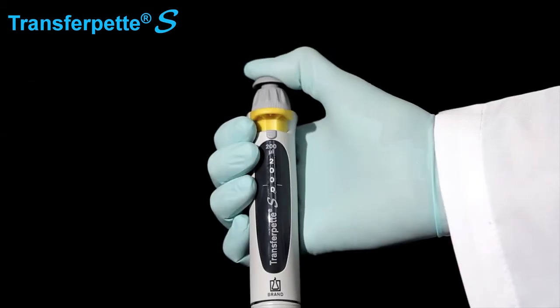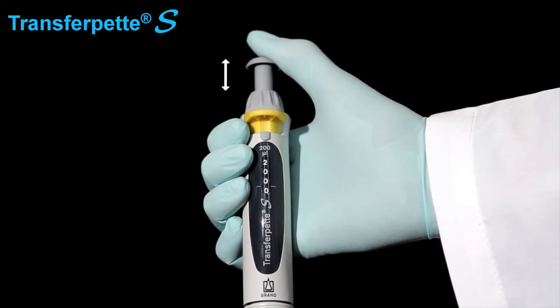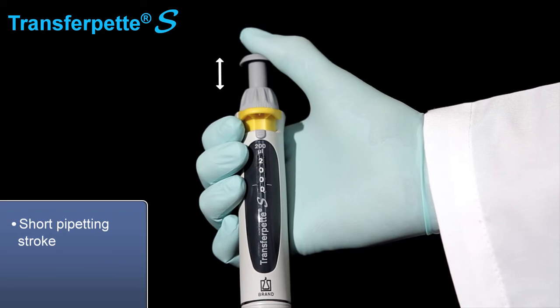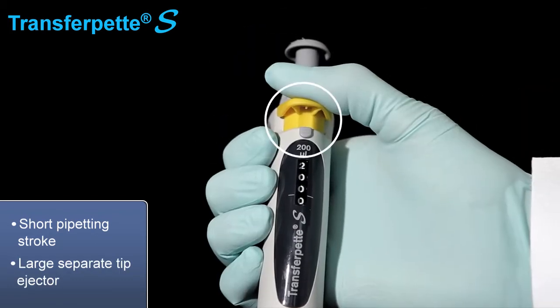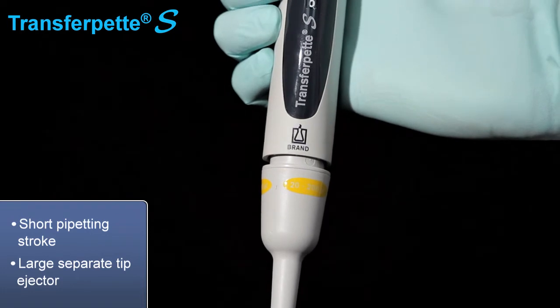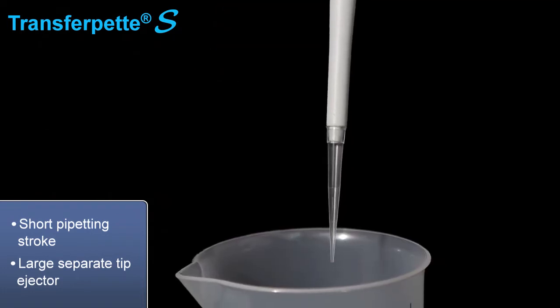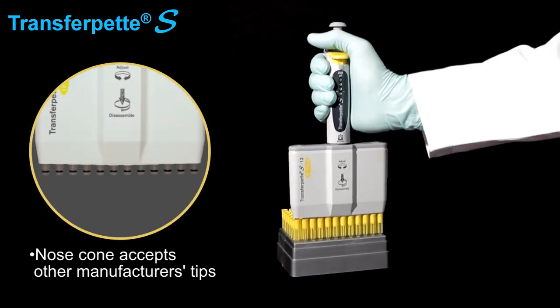The instrument offers a number of user-friendly features, including a short pipetting stroke, which reduces fatigue. A large, separate tip ejector reduces the amount of force needed, enabling easy tip ejection. The instrument's nose cone is designed to accept tips made by other manufacturers.